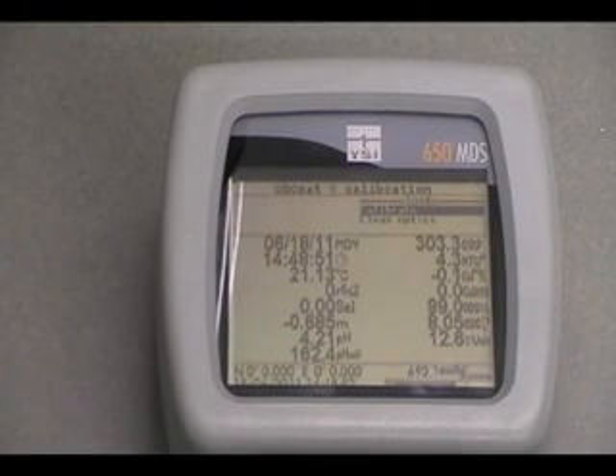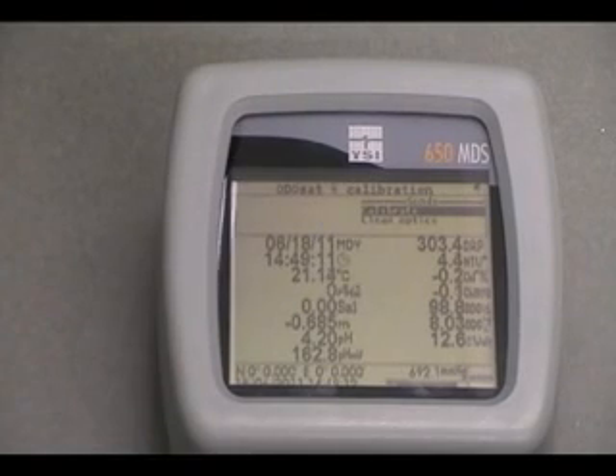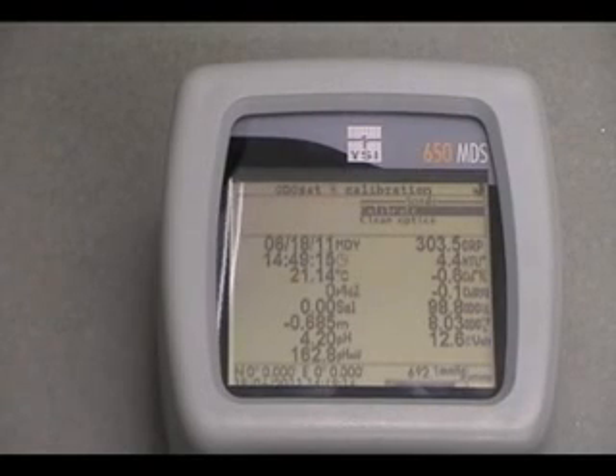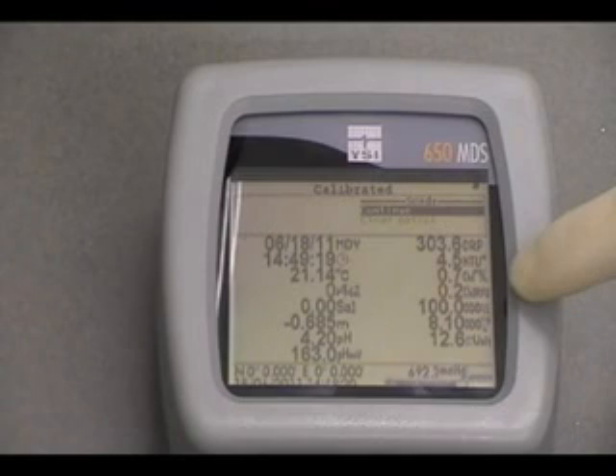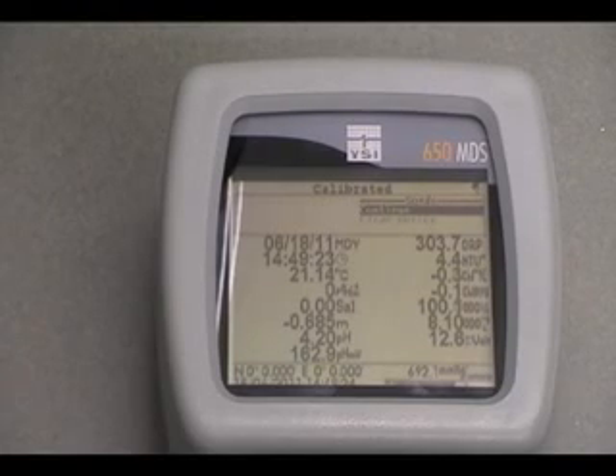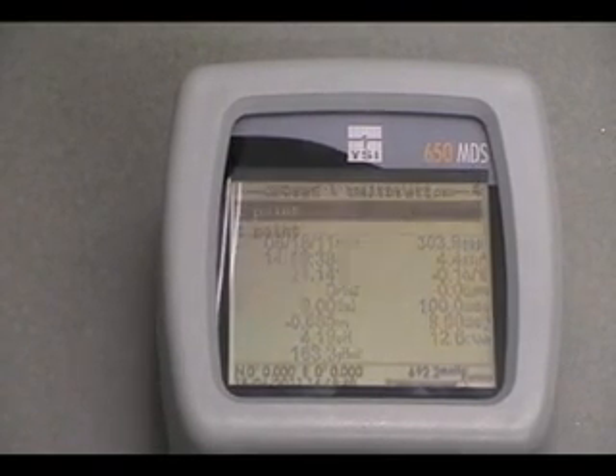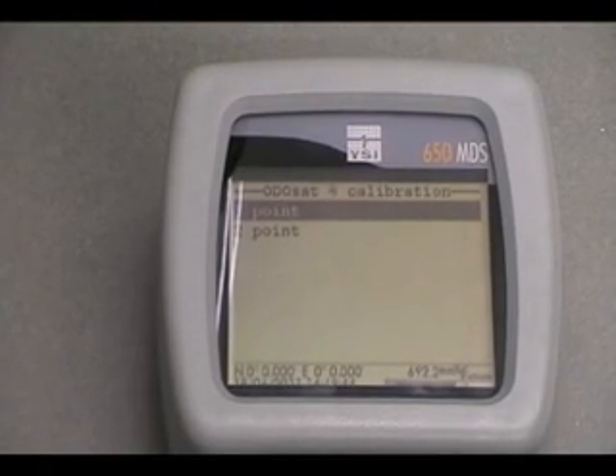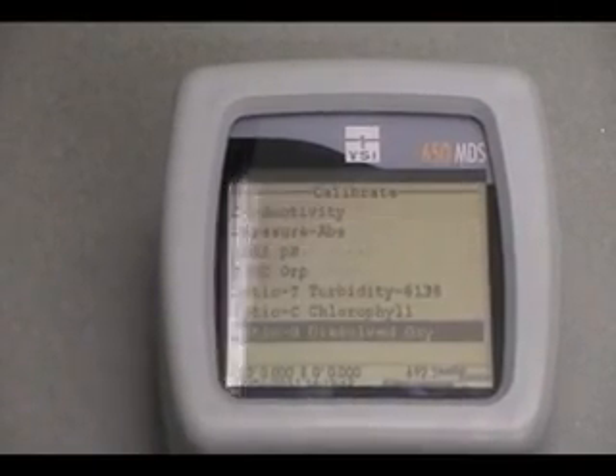Step 8. After allowing the dissolved oxygen readings to stabilize, record the pre-calibration value in milligrams per liter and in percent local on the calibration worksheet. Step 9. Highlight Calibrate and press Enter to calibrate the dissolved oxygen sensor to 100%. Record the post-calibration dissolved oxygen in milligrams per liter and percent local on the calibration worksheet. Press Enter to continue. Press Escape until you return to the main menu.